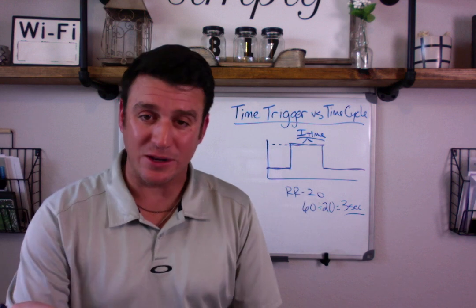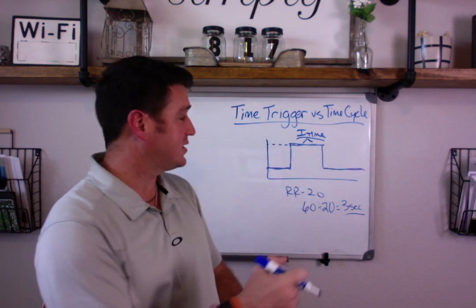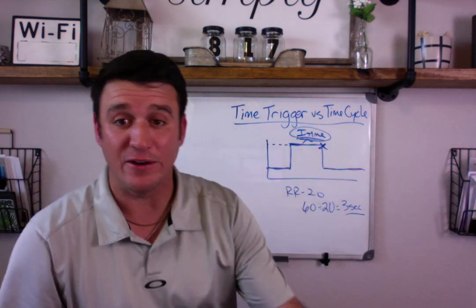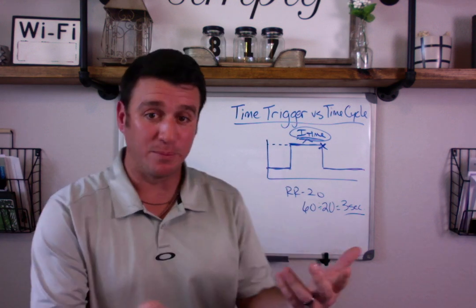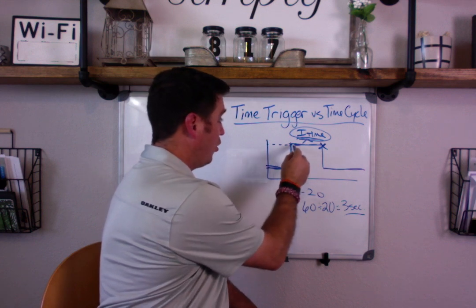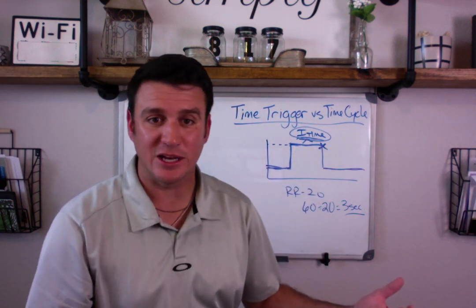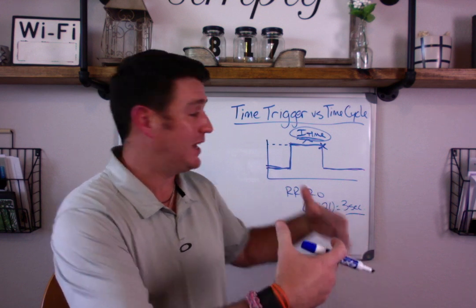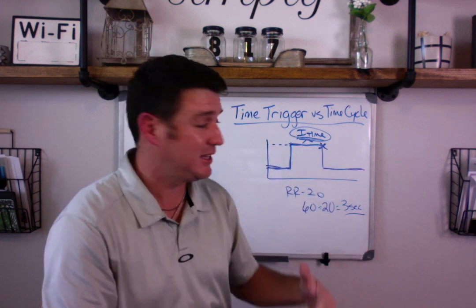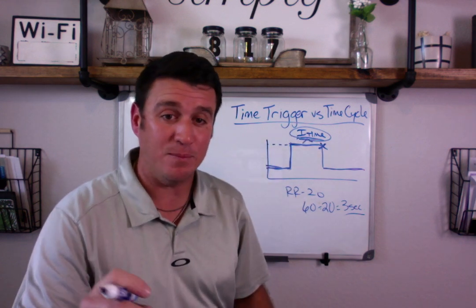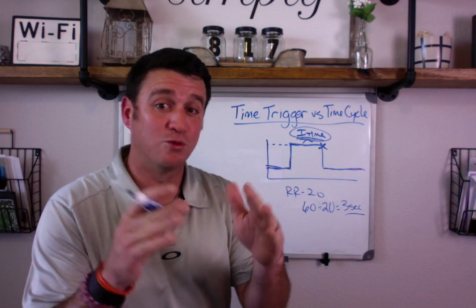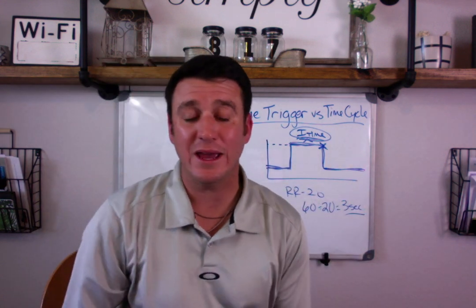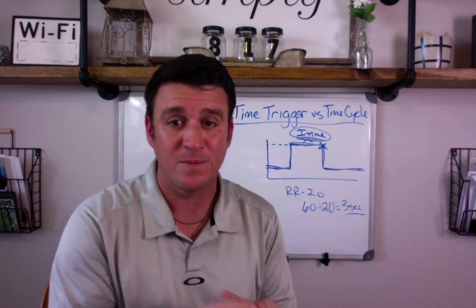When you talk about cycle, you have to understand that what turns the breath off is your set I-time. In pressure control, you set an I-time. The vent is going to give a breath, increase the pressure, and hold it for however long the I-time is set — one second, point eight seconds, two seconds. At the point in time when the I-time has been reached, the vent cuts off and exhalation begins. That's the way time is both a trigger and a cycle.